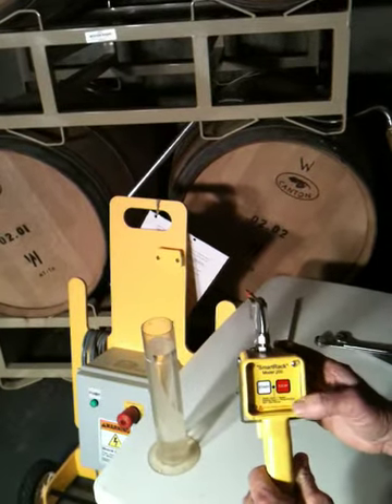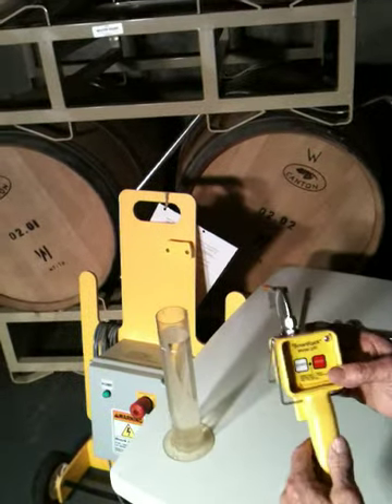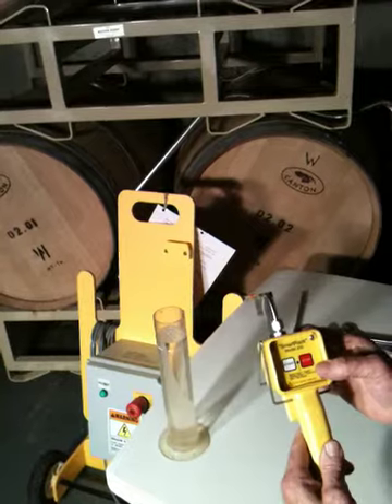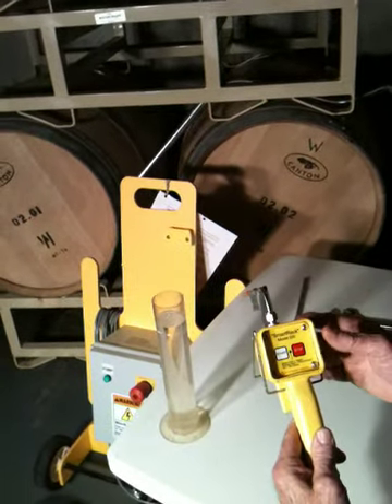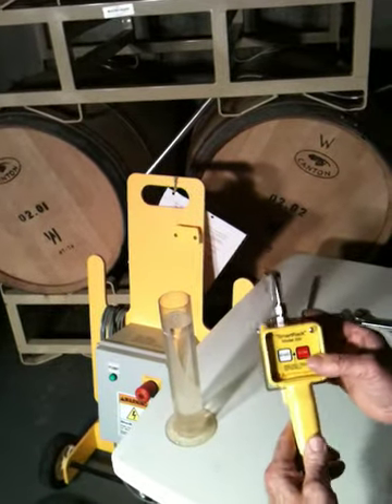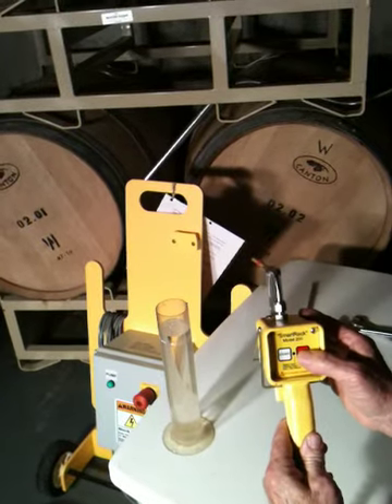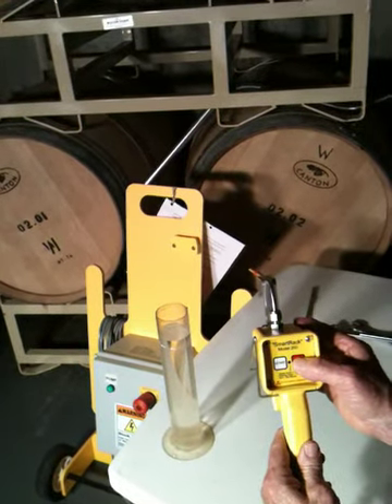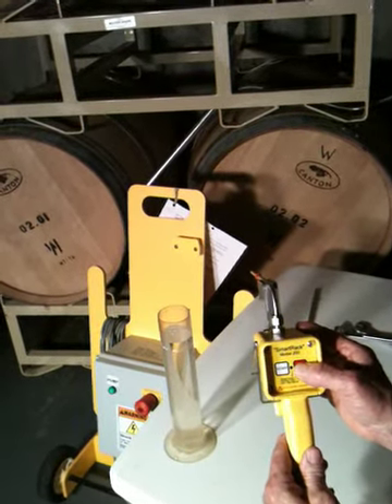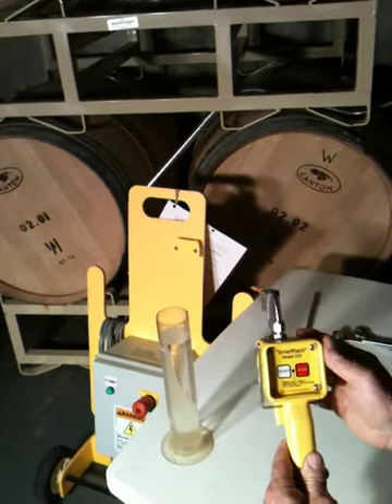Okay, so we hit stop. And now we're in the green steady light. So now what I want to do to go into the calibrate mode, and all this information is in the owner's manual. We press and hold the stop button and hold it down, and it flashes red 5 times and stops flashing. Okay, so now we're in the calibrate mode.